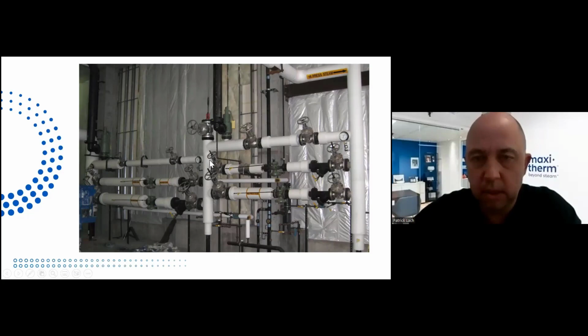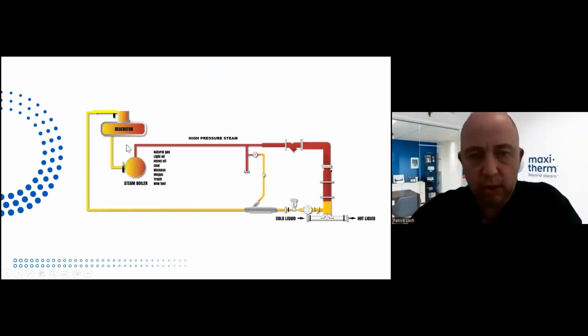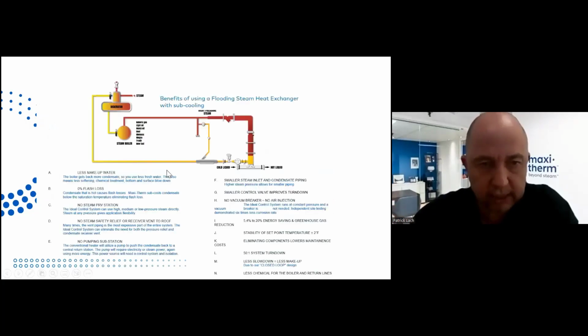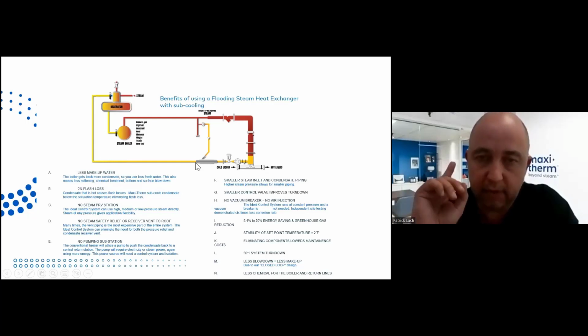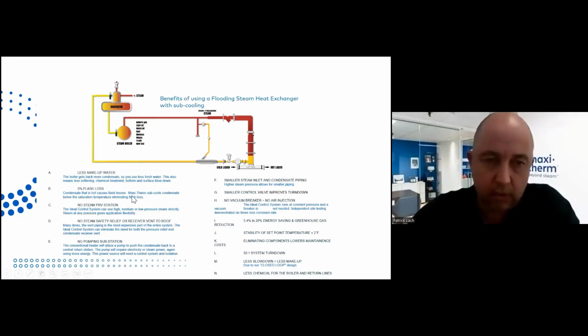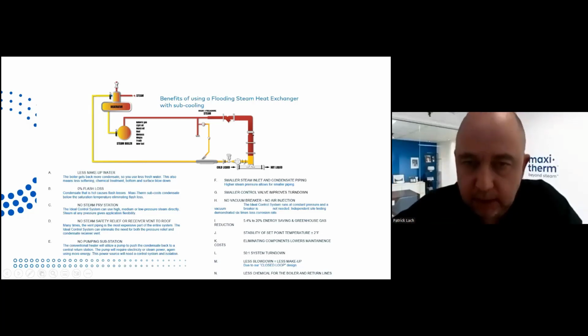All this, all gone. And this is what we do basically, we're coming directly with high pressure steam, again, related to the other video on YouTube, and we control the condensate, full steam pressure, no pressure reducing valve, no more steam safety relief valve, no more condensate pump, etc. So less make-up water by doing so, 0 flash loss. Because condensate, I'll show you, comes out at 200 Fahrenheit and lower at full load, okay? 0 flash loss, no more pressure reducing valve, no more steam safety relief valve, no pumping station, substation, smaller steam inlet on the condensate piping, smaller control valve, up to 10 million BTU process. It's a 1/2-inch control valve.